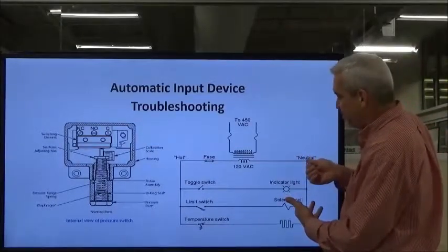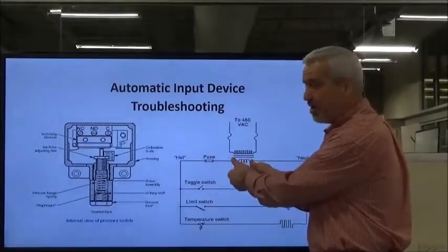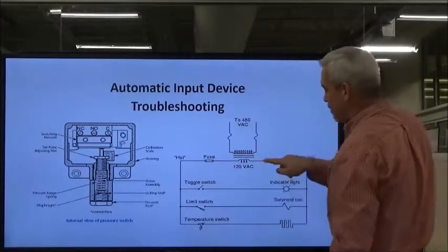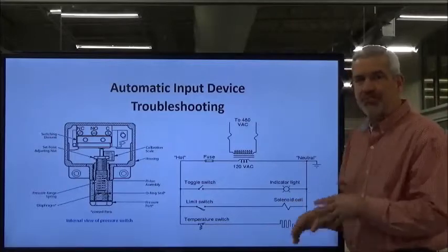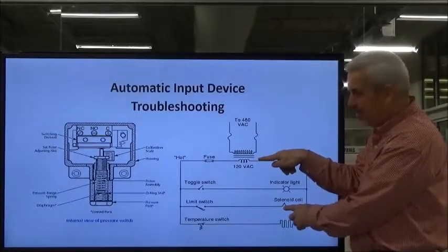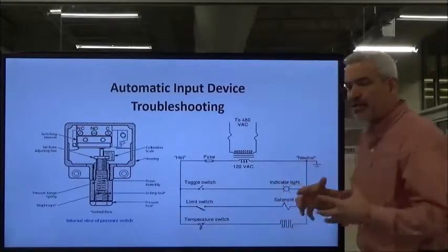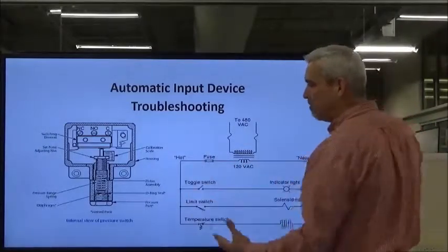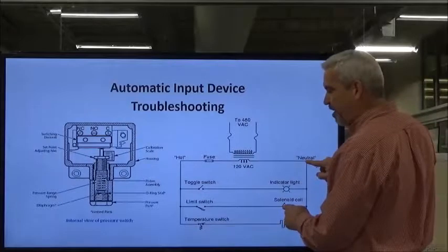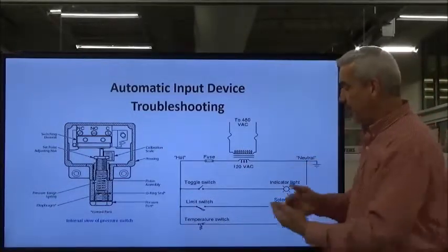You want to get on that transformer as best you can or use a neutral wire that you know is a neutral. What we're trying to do is reference it back to our neutral. So hold your lead on your neutral. In this case, we want a solenoid valve to come on. What do I have to have to get that solenoid valve to energize? I've got to have power. First of all, first thing I want to check, do I have power out of my transformer? Hopefully I do. If I don't, then it's further back up the line. Let's say we've got power. We're trying to get it back home. So we're going to start right here. I want that solenoid to come on. So I've got to provide power to it. Keep it very simple, very logical. Do I have power? Yes or no. If I don't, then I need to start going backwards. There could be 10 limit switches in this line. So what I've got to do is I've got to find out where I'm losing.